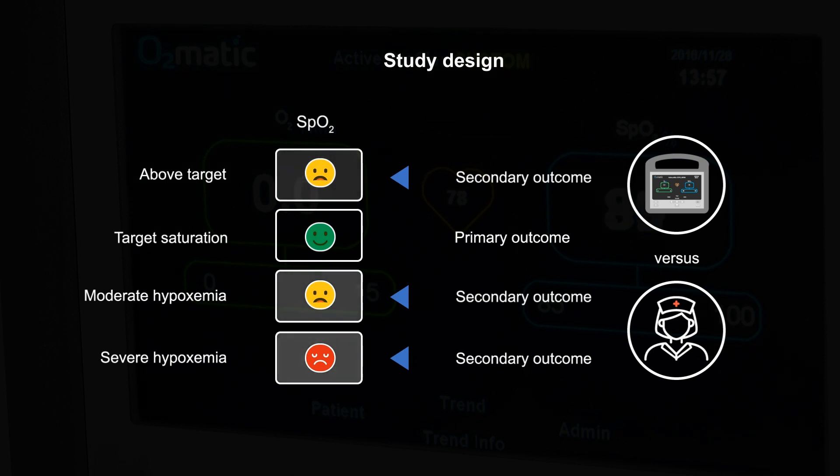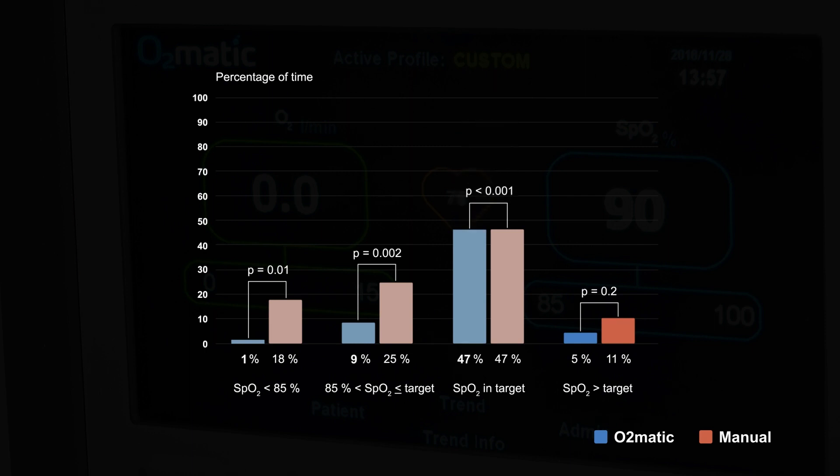Furthermore, we examined patients' perception of automatic oxygen control. The results of the study was that O2matic maintained the oxygen saturation in the prescribed interval 85 percent of the time and manual control only kept the saturation in the right interval for 47 percent of the time.